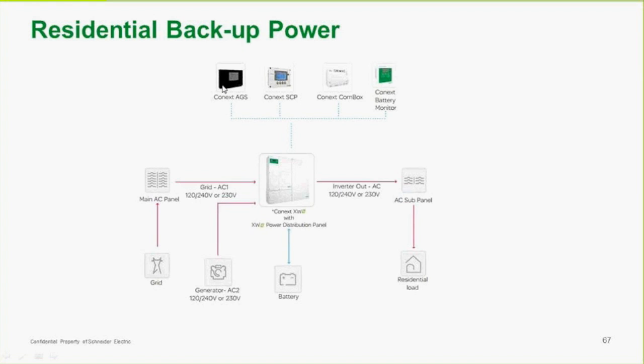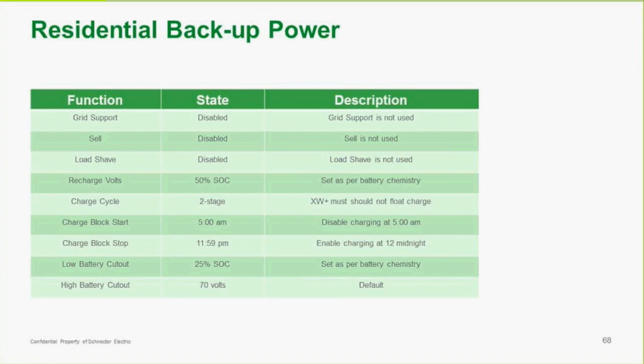We probably have the AGS, the automatic generator start, and we have a ComBox, which is the most common communications device. And we may have a Conext battery monitor that provides more accuracy as far as battery management goes. So in this particular case, we have grid support disabled, we have sell disabled, we have load shave disabled, and we set our recharge voltage depending on the battery chemistry. The charge cycle's at 2-stage. We set a block start time for charging. We have a low battery cutout, and we have a high battery cutout.